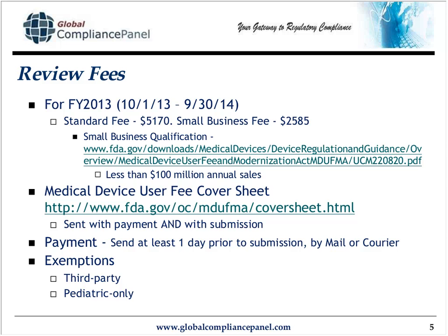There are two exemptions to the requirement for review fees, and these are the devices that are much more important, at least the pediatric-only device. I'll talk a little more later about third-party submissions. Briefly at this point, a third party is a private company to which you submit your 510K, they review it, and they have been licensed, authorized by FDA to grant you clearance. So we'll talk a little about that. You have to pay for that service, so FDA realizes that you shouldn't have to pay twice for the same service.